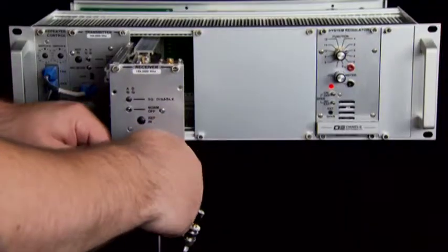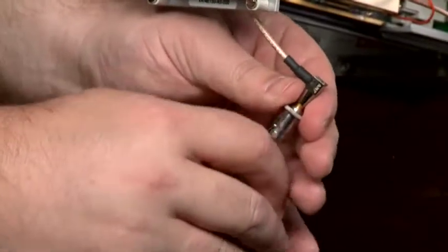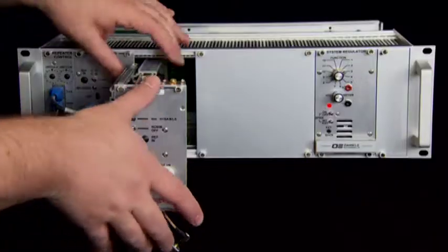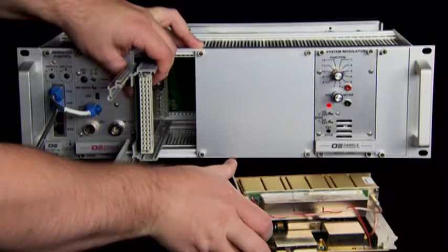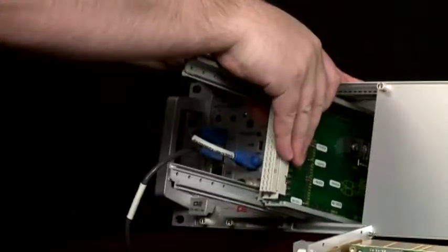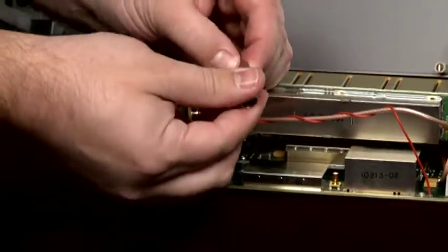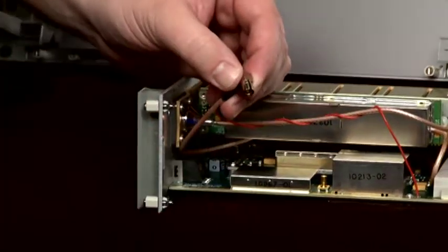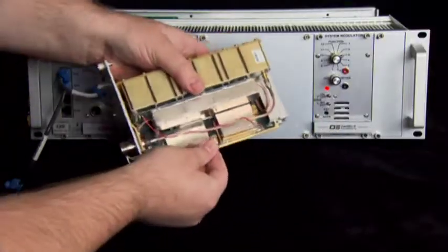Remove the RF cables from the RF input and RF preselector output. Remove the receiver and extender card from the sub rack. Remove the SMB to BNC adapter from the RF preselector output and reconnect the SMB plug into J3 on the receiver mainboard.